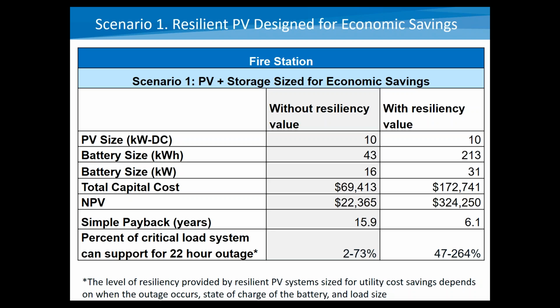And then you can see in the right column, titled with resiliency value, that the system sizes change when you include the cost of grid interruptions. So in this case, we're again sizing the PV system at 10 kilowatts, and you might remember that's the maximum size that can fit on this rooftop, so you really can't have a larger system at this site. But the battery size increases quite a bit, so it goes up to 213 kilowatt hours and 31 kilowatts.